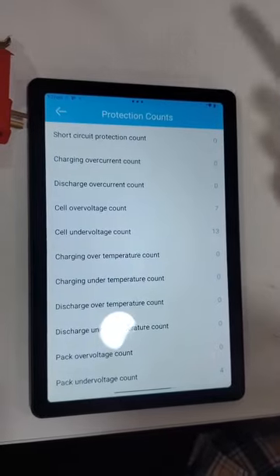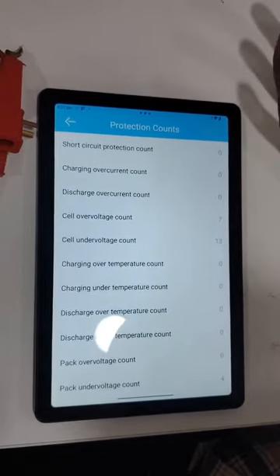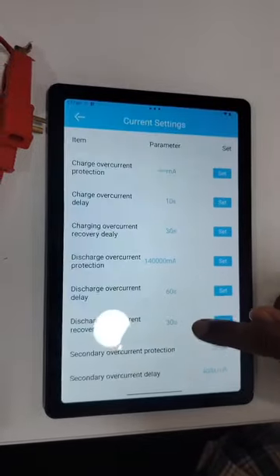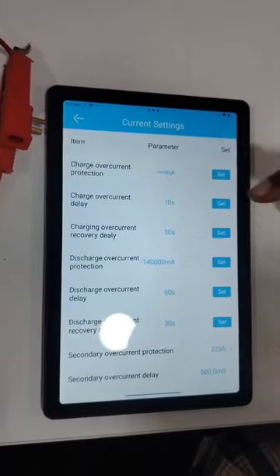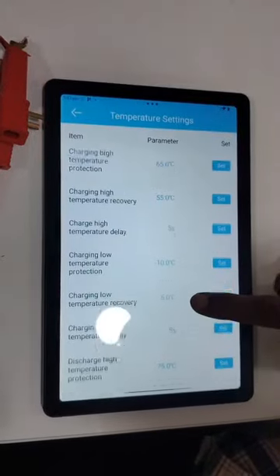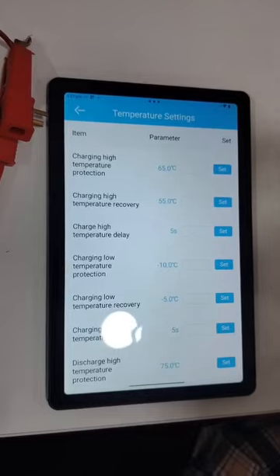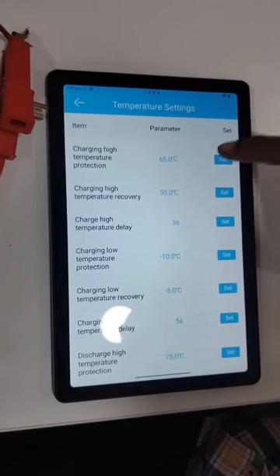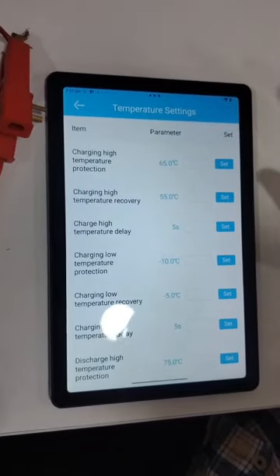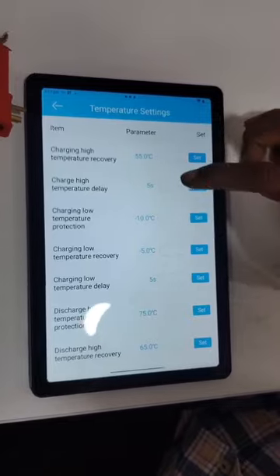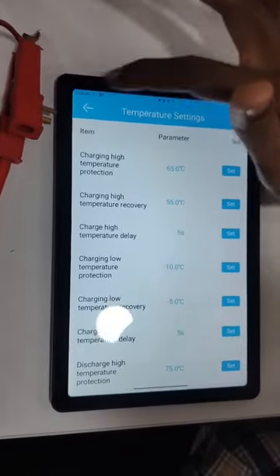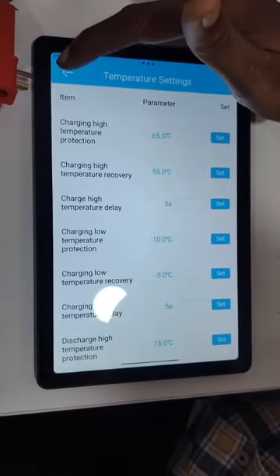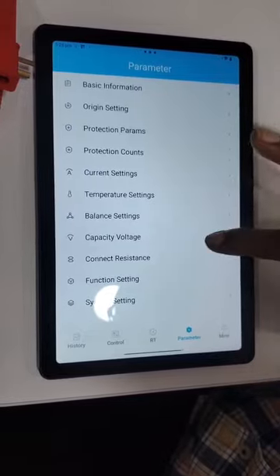Then we have protection counts. You can set how many times charging, discharging, overcharging, undercharging can happen, and that also it automatically counts. And then we have current setting. Similarly to the voltage, we can set the values for current as well. Okay, this is the current setting. And then we have temperature setting. What should be the maximum temperature the battery should reach? If the temperature goes beyond that, the BMS will automatically shut off the charging or discharging mode, whatever it may be. So you can set that value. After that temperature is reached, the BMS will automatically switch off the particular charging or discharging mode.